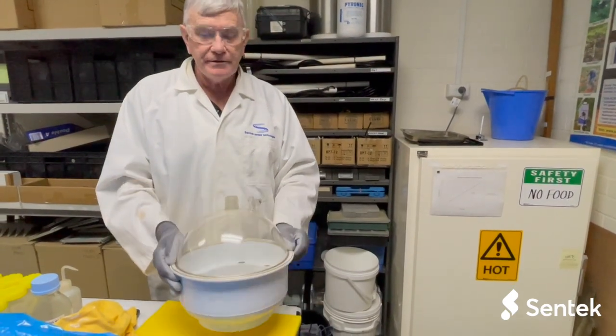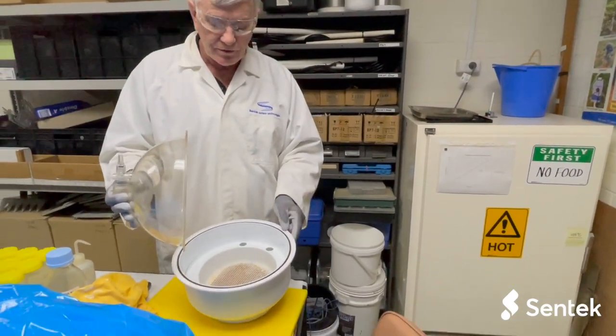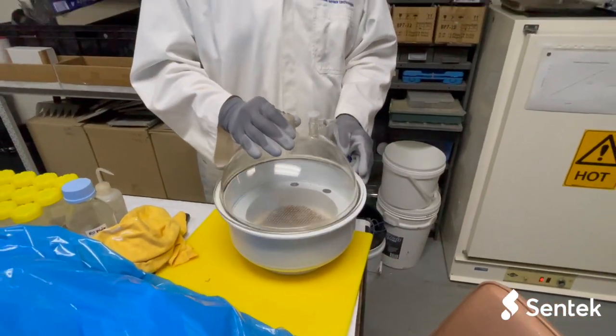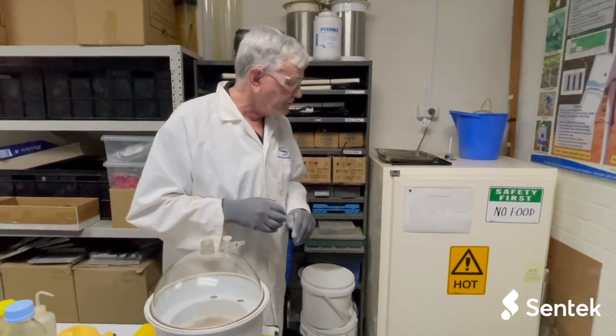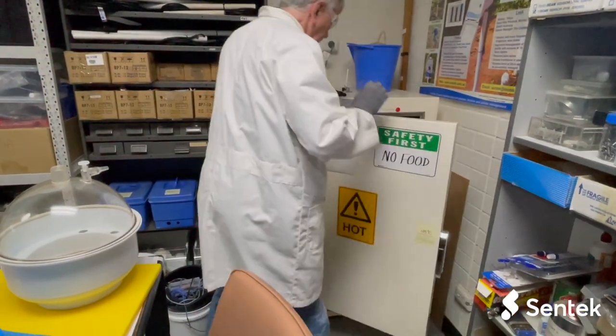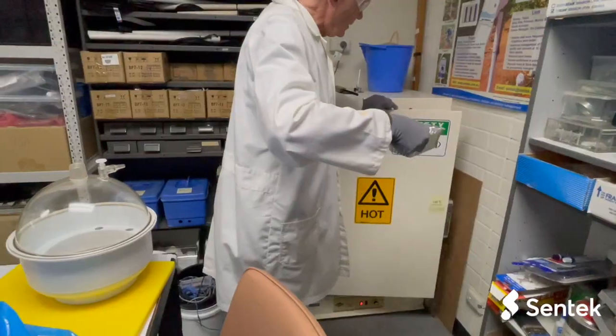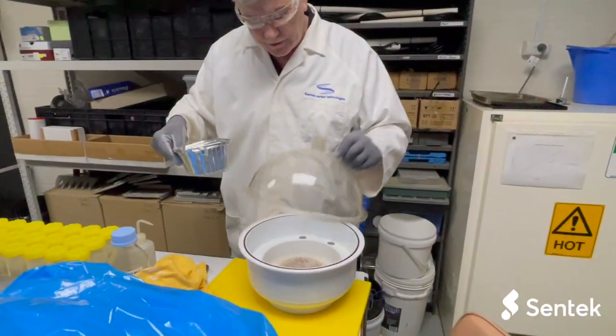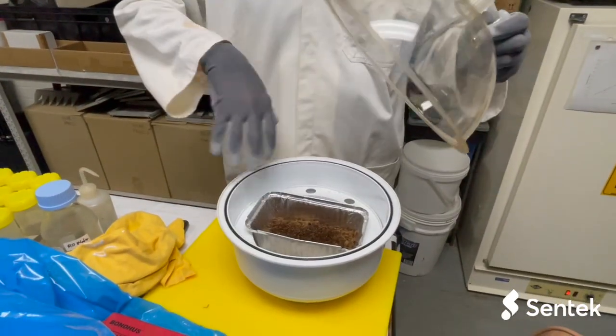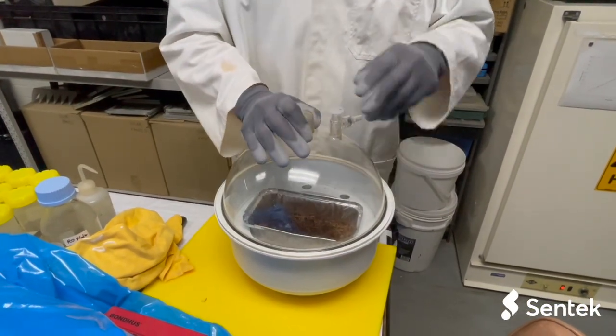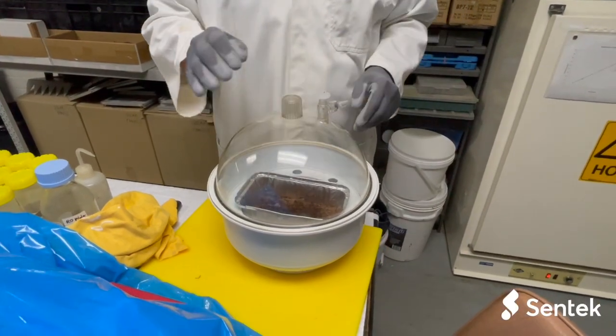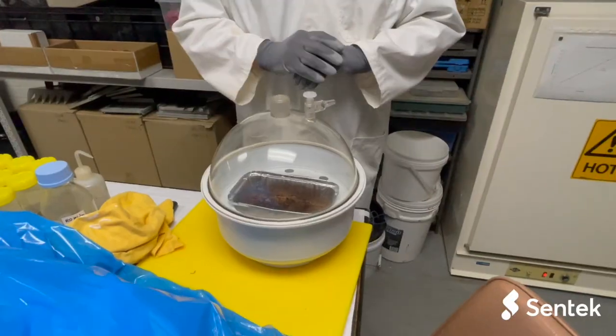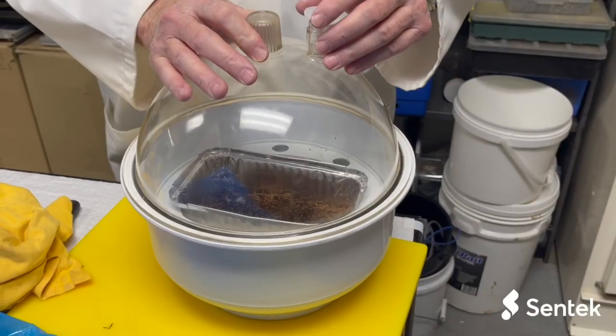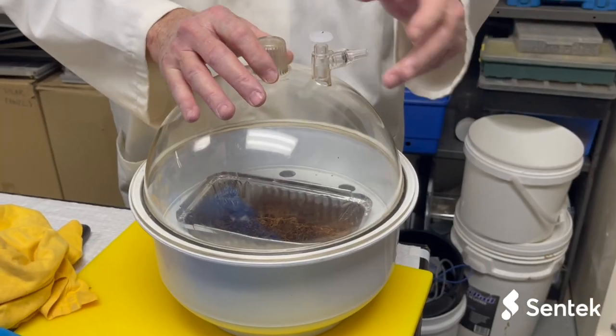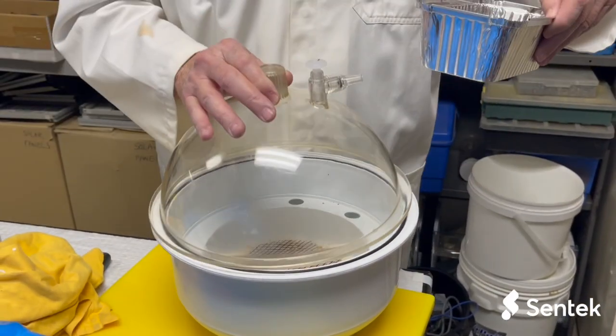Okay, so if we're ready to take a reading of the weight as it's drying, we use a desiccator like this to place the sample in. That will allow a sealed environment for the sample to come up to temperature. So we take that from the oven. That will go in the desiccator. You'd have 3 or 4 of them. Just put that one on and you close the environment there, and you'll leave that for half an hour to an hour. So to break the seal, you open that up and then take your sample out.